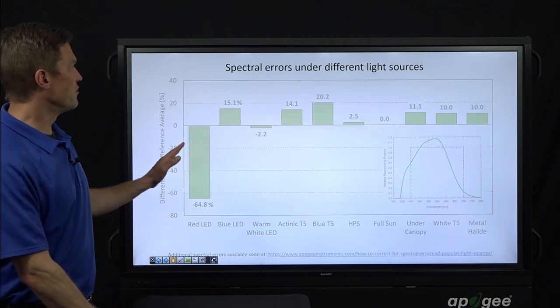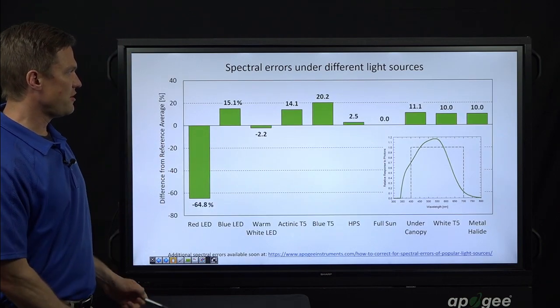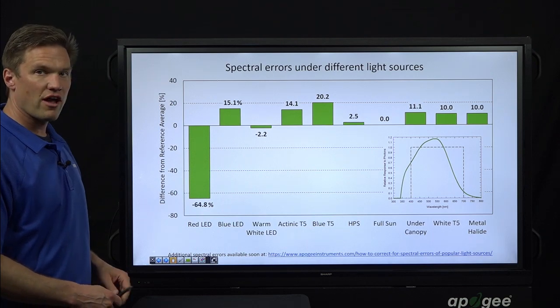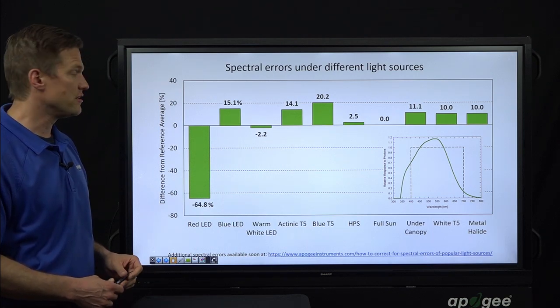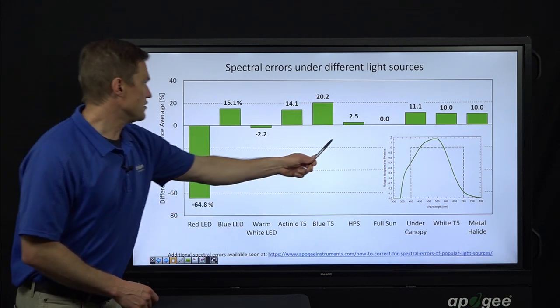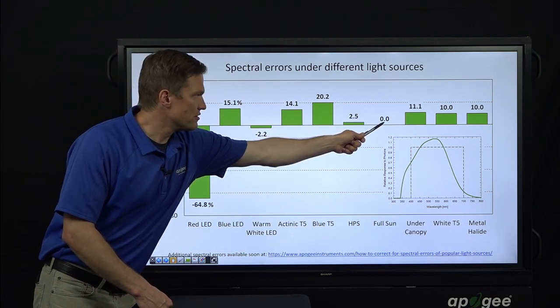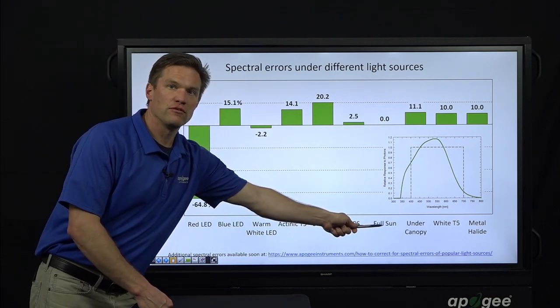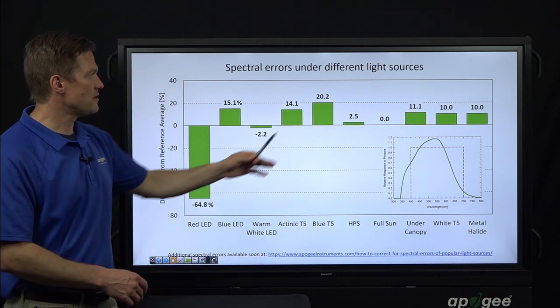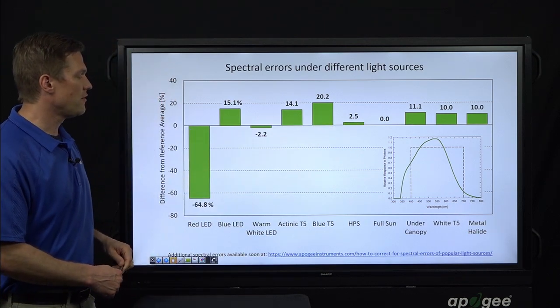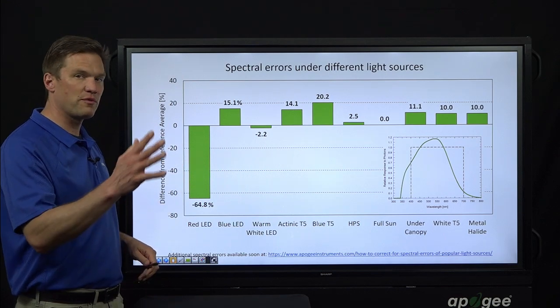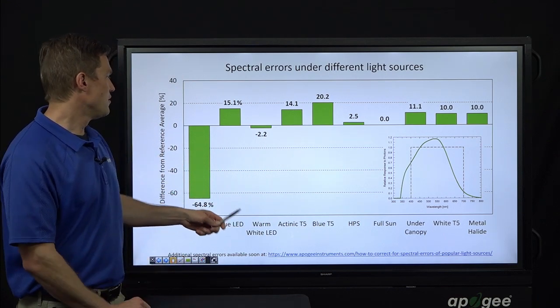For sunlight, they're going to be spot on, calibrated well. Under electric lights, there are some errors to consider. And here's a summary graph showing some errors for some commonly used light sources. I'll start over here 2/3 of the way through with a 0 error under full sun. So they're calibrated to sunlight, so it makes sense there's not going to be error on the signal in sunlight. Solar spectrum is what it's calibrated to.